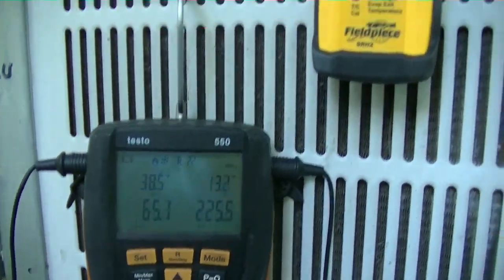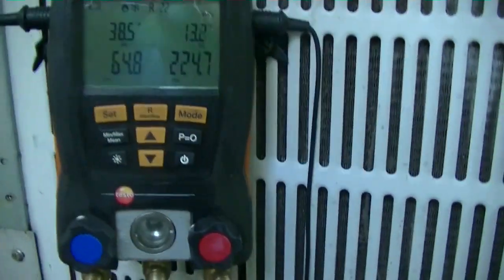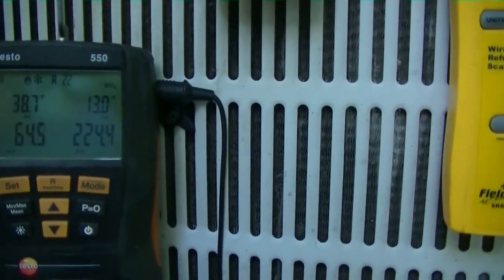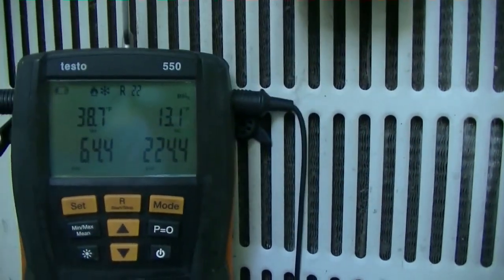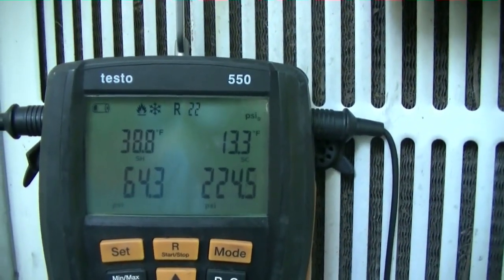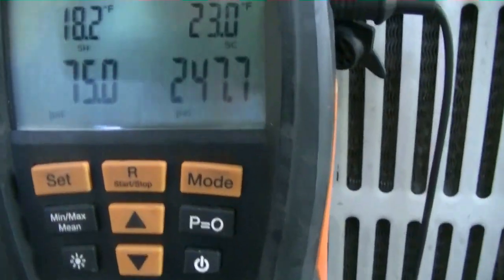This is real-world stuff here — this is not a classroom. It's bad when you don't have a data plate to tell you how many ounces it holds or anything. You just do what you can with what you got. I've already unhooked my scale and everything, but it took about 10 pounds.